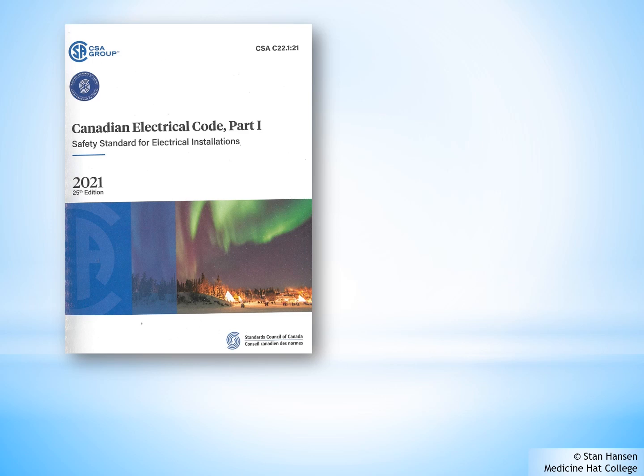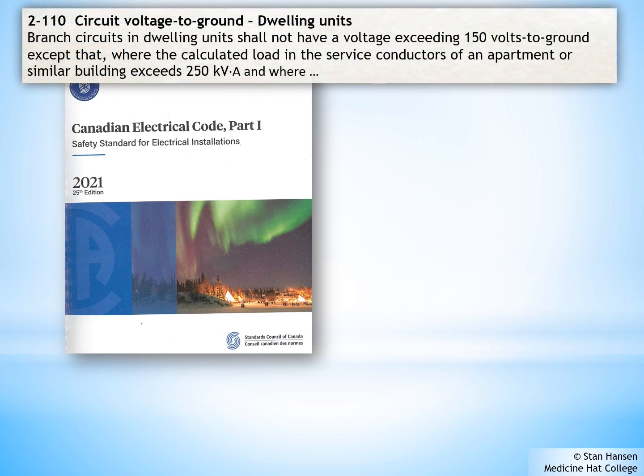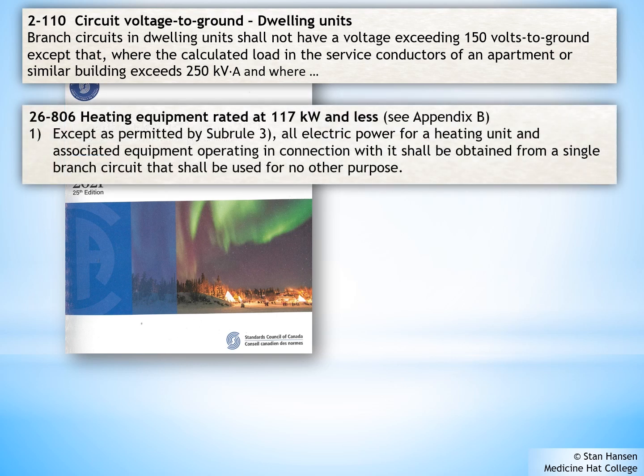We start with Rule 2110, which tells us the maximum voltage to ground for our furnaces cannot exceed 150 volts. Which is good because that's the system voltage that we have for our houses anyway. Rule 26806 states that any heating equipment rated at 117 kilowatts and less, which is our typical gas-fired furnaces, must have its own separate branch circuit. It also says that any associated equipment can also be on that same circuit. So we would be talking about things such as humidifiers, electronic air filters, HRV units, and UV filters. Check out Appendix B on that rule.